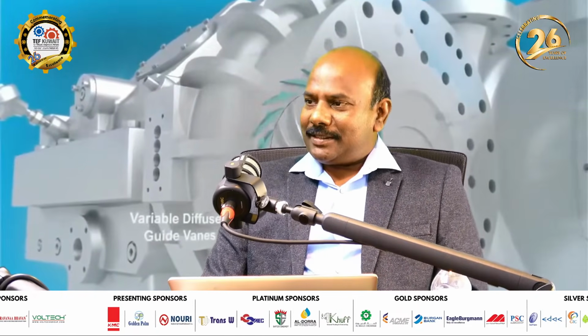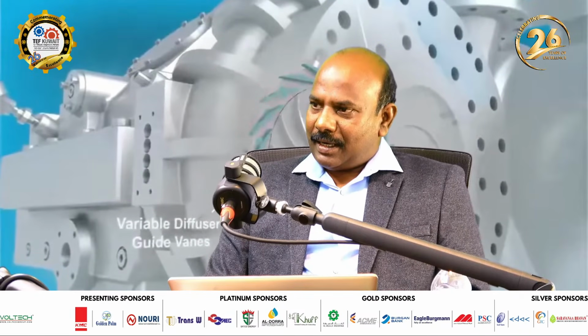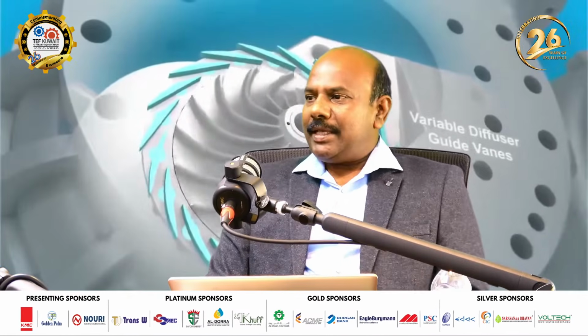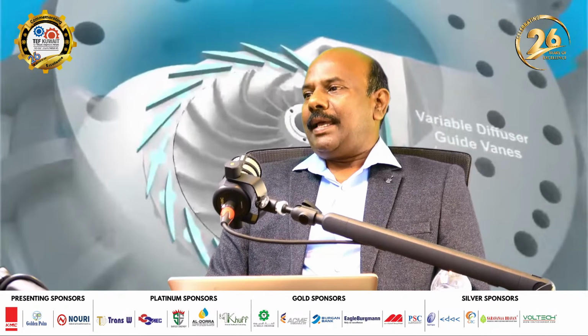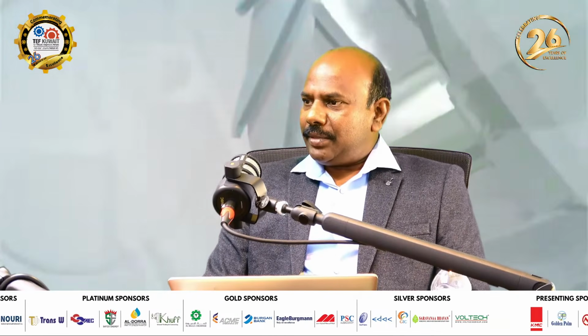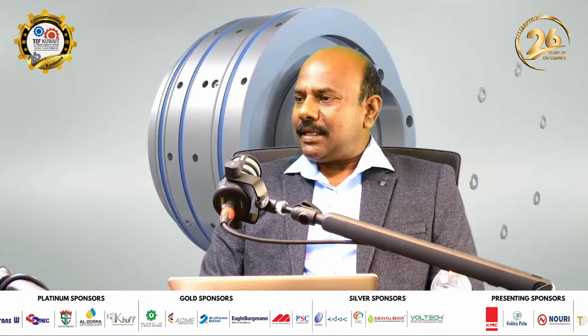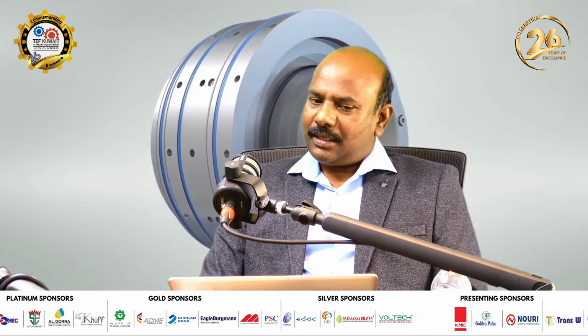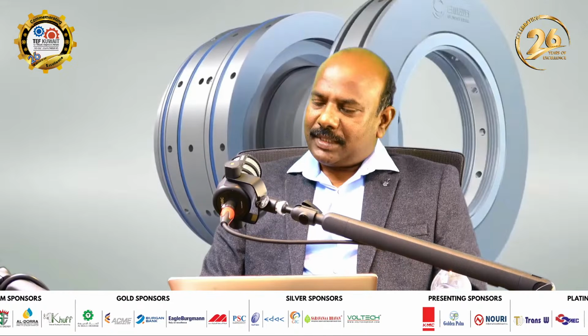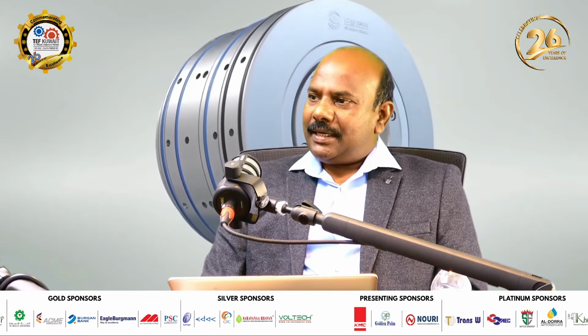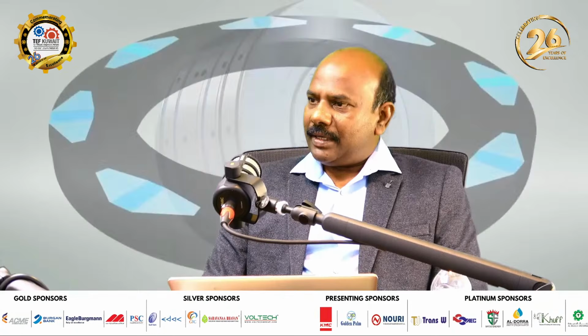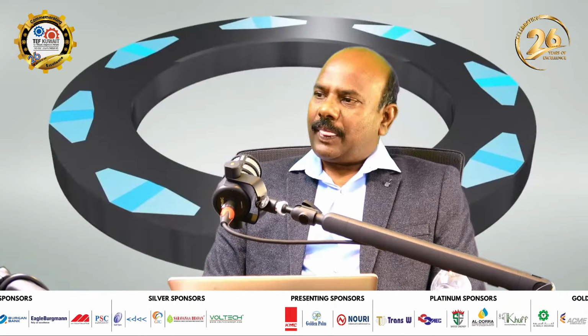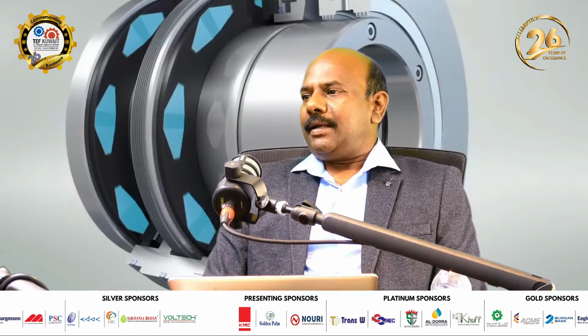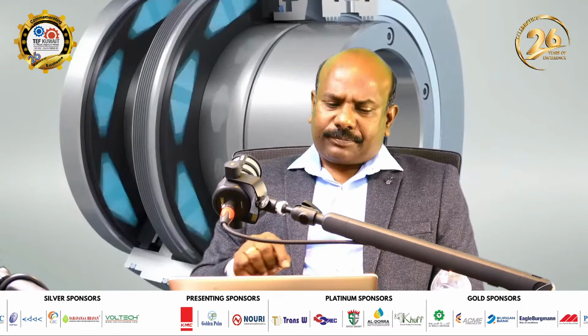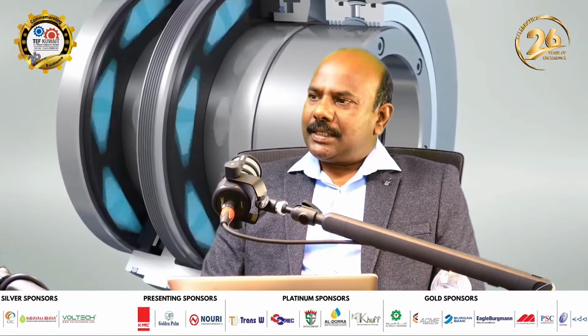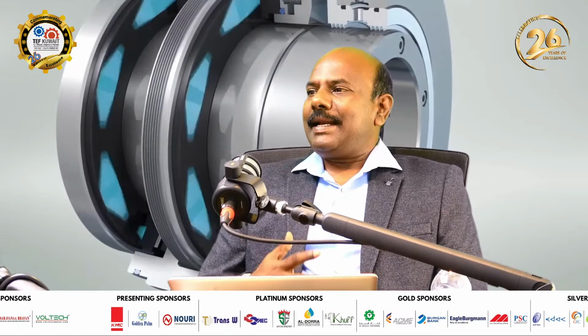Nowadays those things are replaced with hydraulic governors, and now these hydraulic governors are again replaced by electronic governing systems. This electronic governing system is very simple, taking input from speed sensors, and with state-of-art control systems, turbine speeds are controlled in a very efficient and precise way. Even the overspeed trip system for turbines has changed from mechanical to electronic, enabling a higher level of safety.